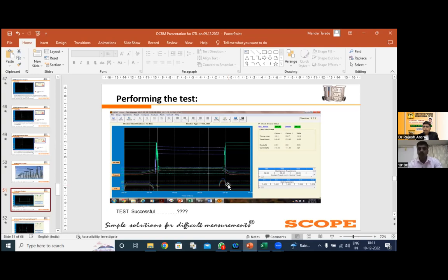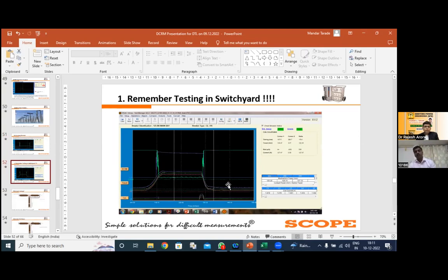So here you have already received all the 3 traces of the trip coil current for the R pole, Y pole, and B pole. Individual breaks are also available. So according to that, the graph is in front of your screen. Now, I already told you that we are performing the entire testing in the live switchyard. So whenever you are getting a sinusoidal wave, particularly on your resistance curve, then we need to understand that the 50 Hertz noise is coupled on your signature.